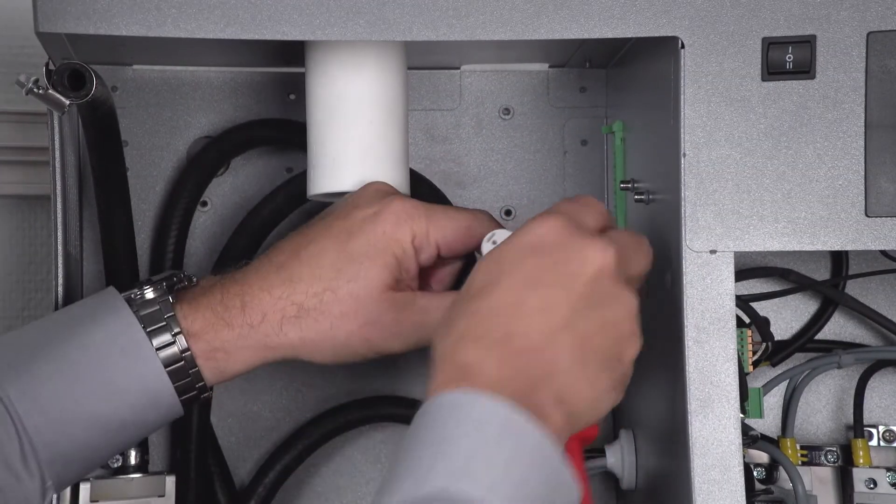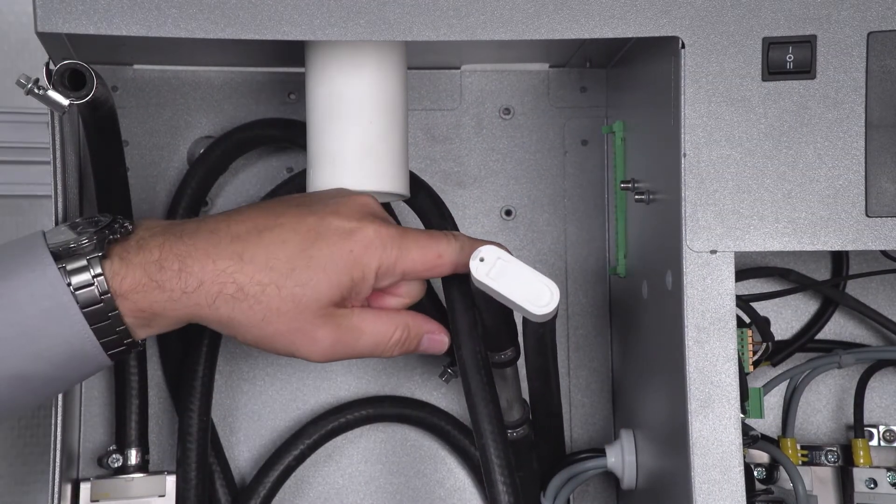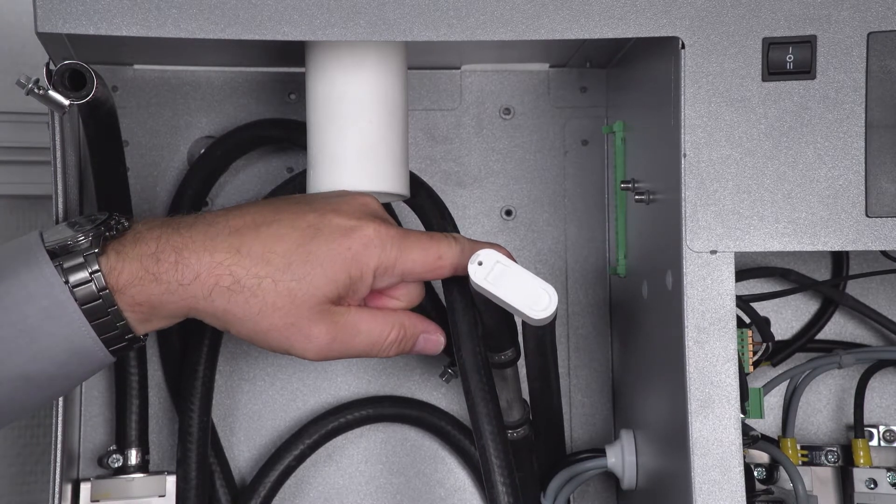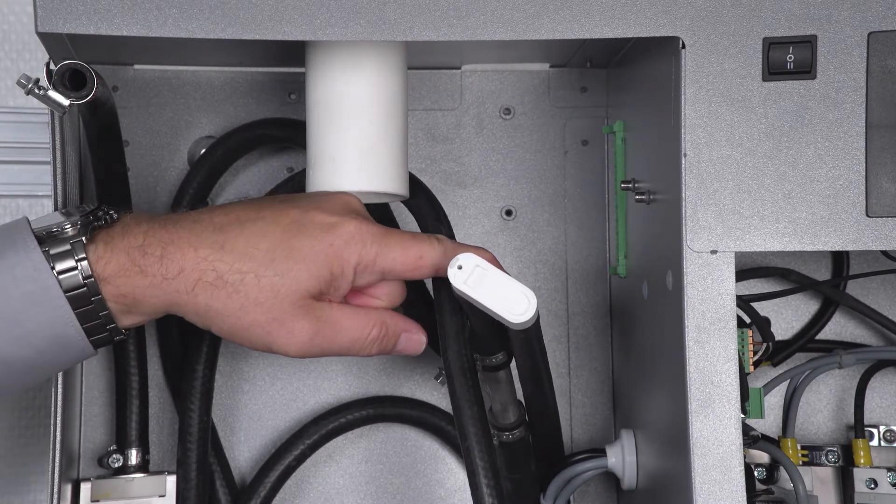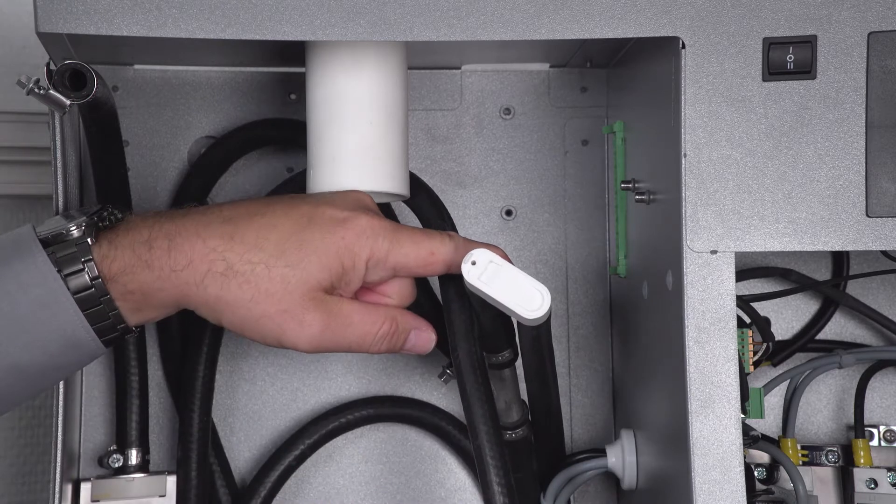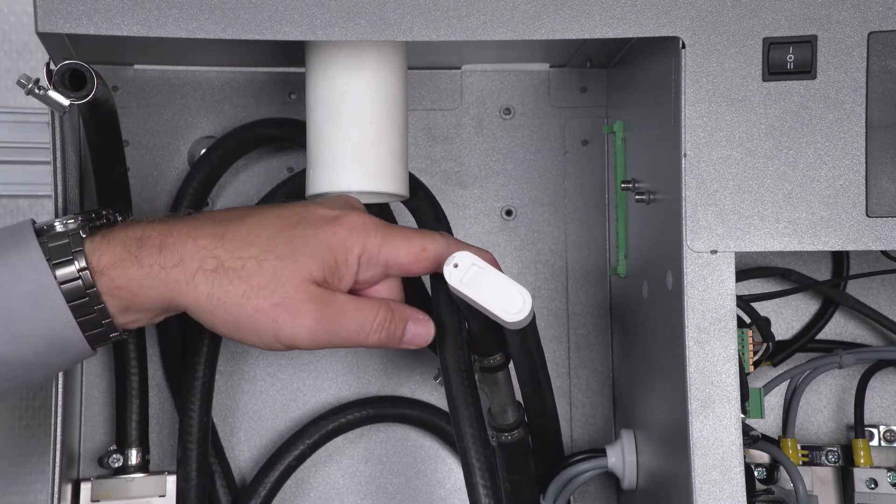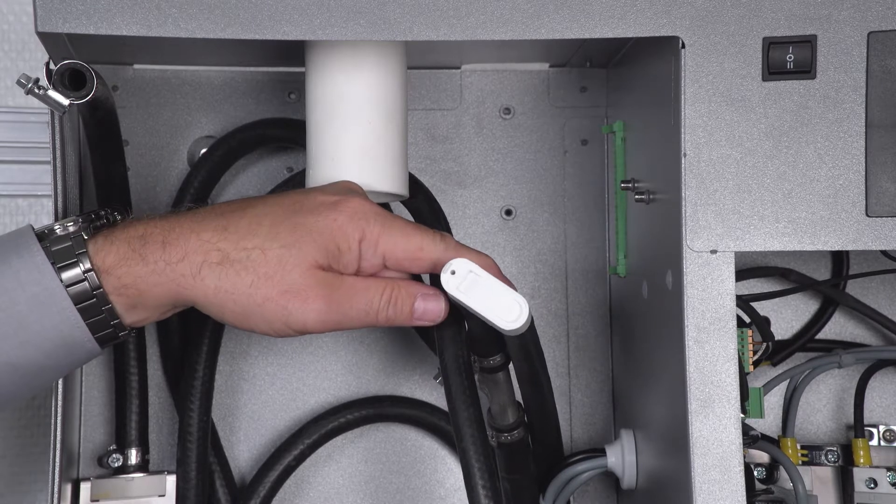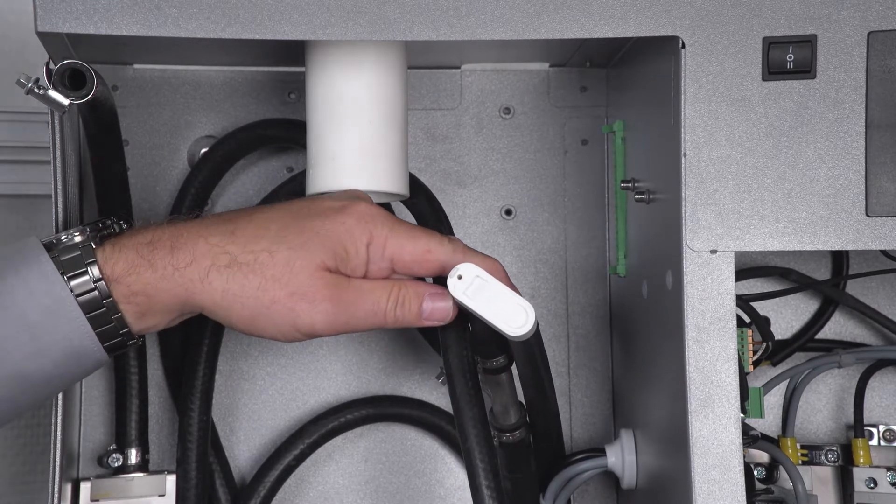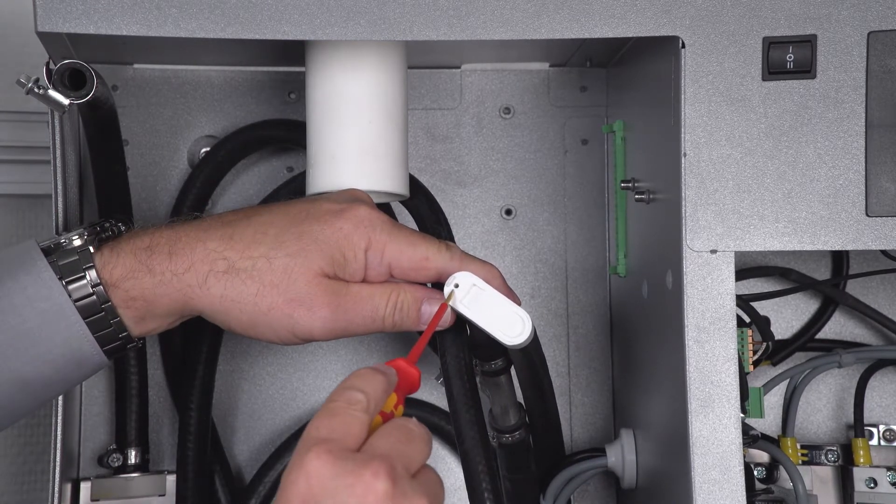The pipe bend, which makes the water that the blow-down pump drains out of the steam cylinder flow out, is redirected here via this pipe bend. And I must make sure that this small vent, seen quite well here, is free of residue.